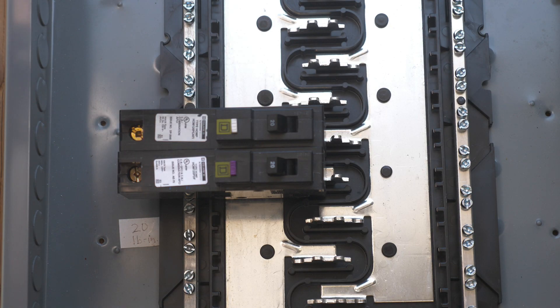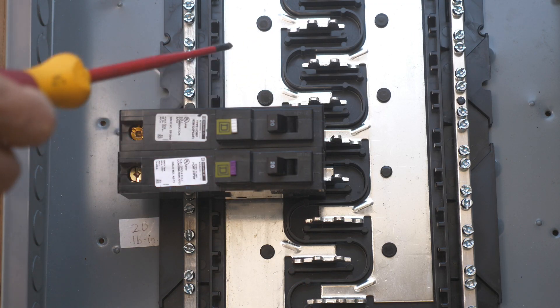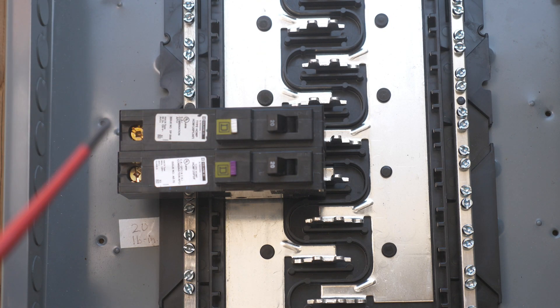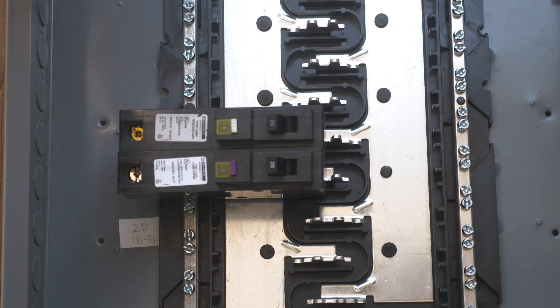This happens to be a Homeline panel right here and it is not energized at all. I'm still using a thousand volt insulated screwdriver to point things out. So this is your CAFCI combination arc fault circuit interrupter breaker right here. And this goes with this plug-on neutral panel. You see this is a neutral bar here, and this is a neutral bar here. This is a Homeline system where there's a space right here, and you can just take these off like that.